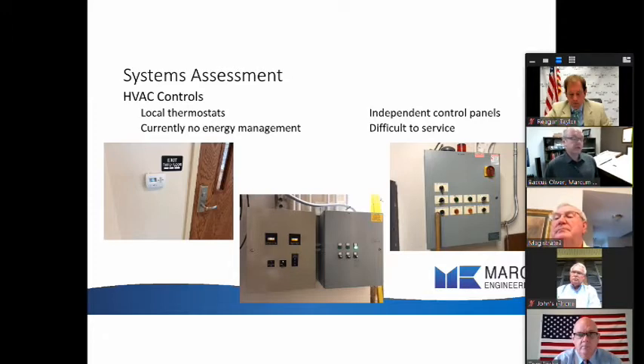Then you got lots of control panels. Basically, there's a control panel dedicated to each major equipment function. There's one for the cooling system on the roof. There's one for the DOAS on the roof. There's one for the heating system in the basement. These things are all working on their own and not working together collectively for energy management. So this has made it very difficult to service. This has made it very difficult to get temperatures set. So I believe this is our second contributor to being uncomfortable, is not having the type of controls that we should have for a building that's so large.